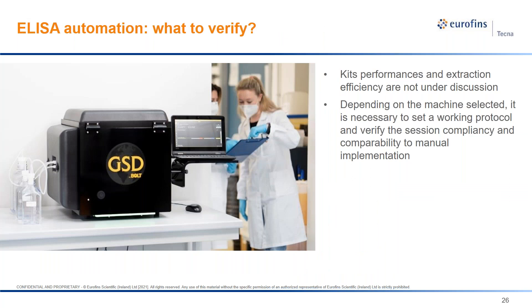Thank you, Evelina. 'What to check' is exactly the right point. An automatic analyzer substitutes the manual implementation, so it does not affect the extraction efficiency at all and should not affect the binding reaction between the toxin and the antibody — the performance of the assay should not be under discussion. On the other hand, a plate analyzer is not a human being and acts differently. It should be verified whether the instrument is capable of obtaining comparable sessions with comparable or better results than those obtained manually.